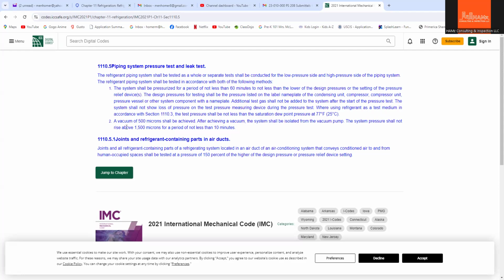After that, for some jobs we need to have a vacuum test for 500 microns. This is a negative pressure. They have particular gauges to be used for this, so we also need a calibration certificate for that particular pressure gauge. This is a vacuum pressure. This is another test requirement in case your job requires it. So this is the requirement.